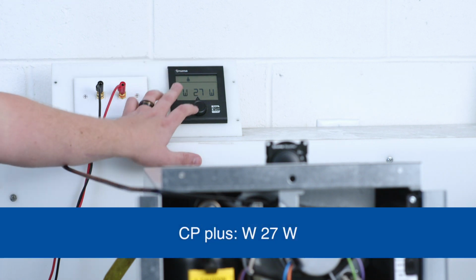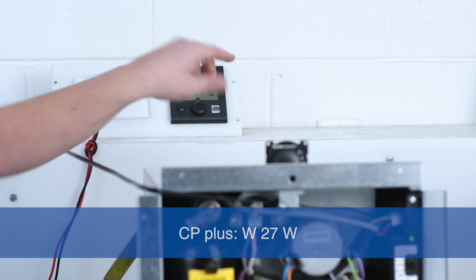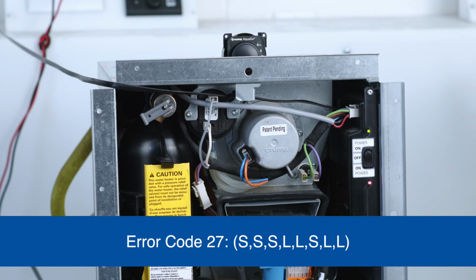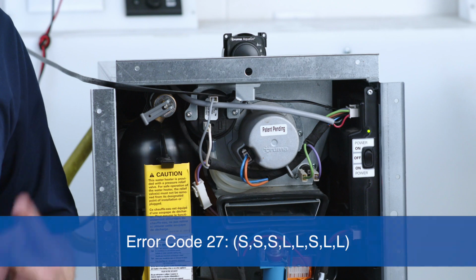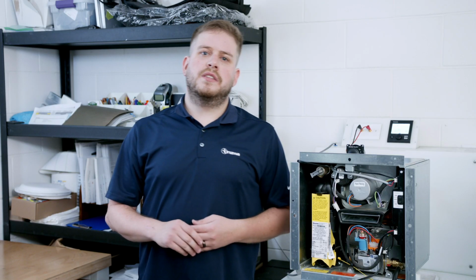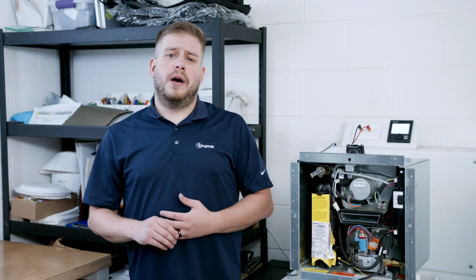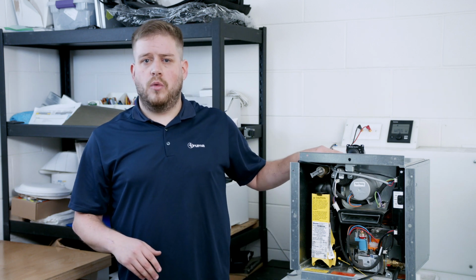The next most common error code we hear about here in the call center is error code 27. On your CP Plus, that's going to be displayed as W27W. On the dial control, the board will flash the error code as 3 shorts, 2 longs, 1 short, and 2 longs. Error code 27 means that the circulation pump is running dry. There is no water within the circulation loop of the water heater.